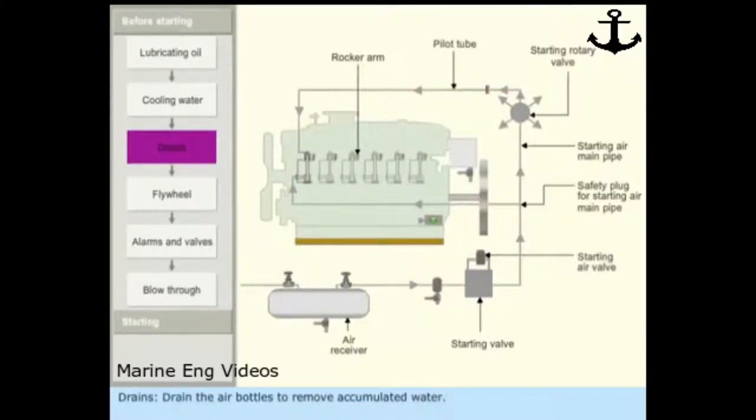Drains: Drain the air bottles to remove accumulated water. Drain moisture from the start airline drain cocks. Drain the air coolers to check for water accumulation.